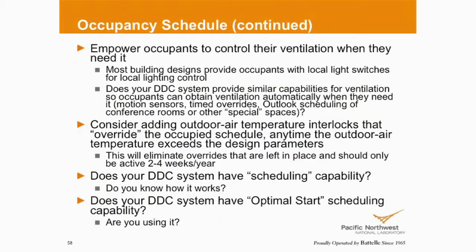And how many of you manage or watch overrides on your BAS systems? I'm not going to ask you to raise hands, but at my site, we constantly battle overrides. And overrides are a good thing. It's what the operator uses to take immediate corrective action. The question is, do they go back and correct the root cause, or is that the Band-Aid? Overrides are becoming the Band-Aid for a lot of things that have deeper problems.